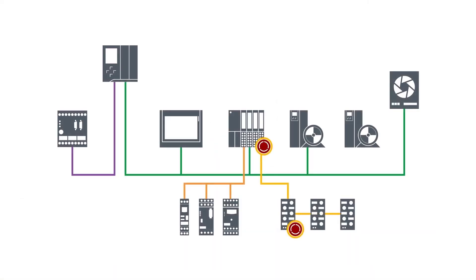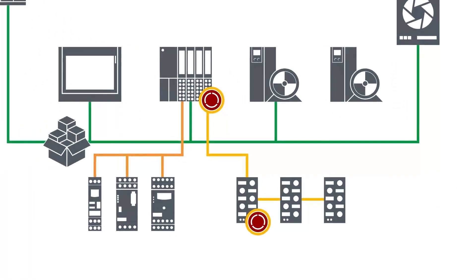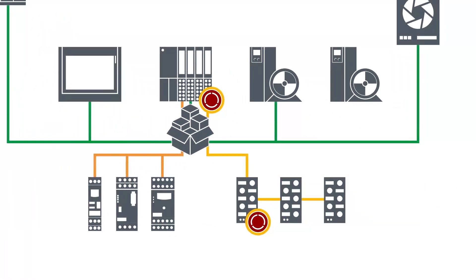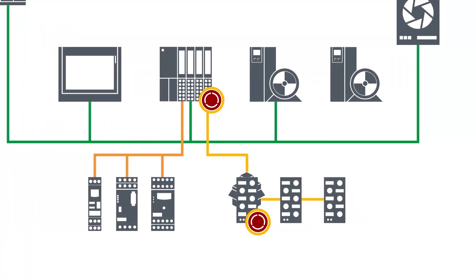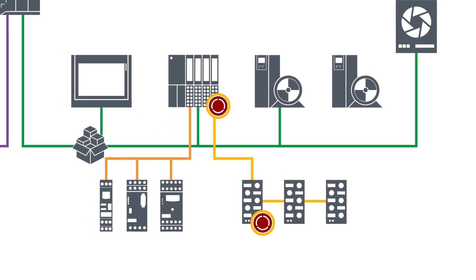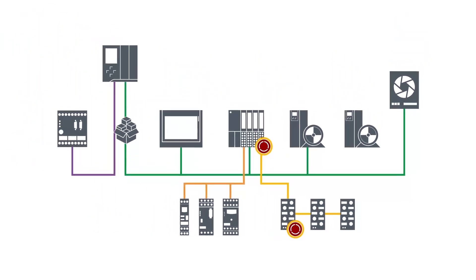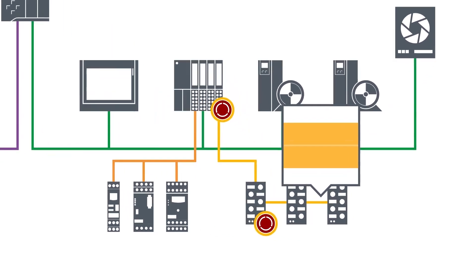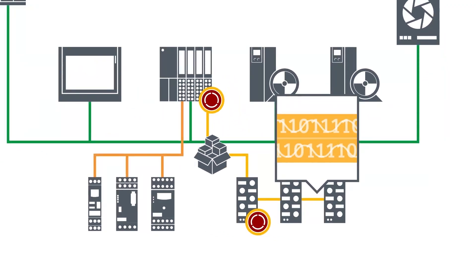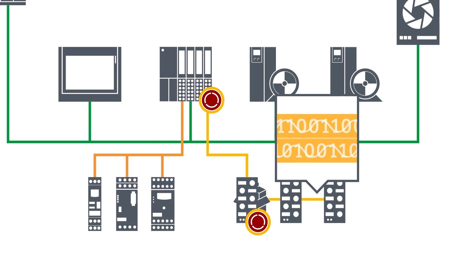Now let's take a look at ASI and I.O. link, which are often found in the field level. The bus system ASI is usually seen as a feeder for PROFIBUS and PROFINET with minimal wiring. A single two-wire line designated as a bus is sufficient for the power supply and communication.